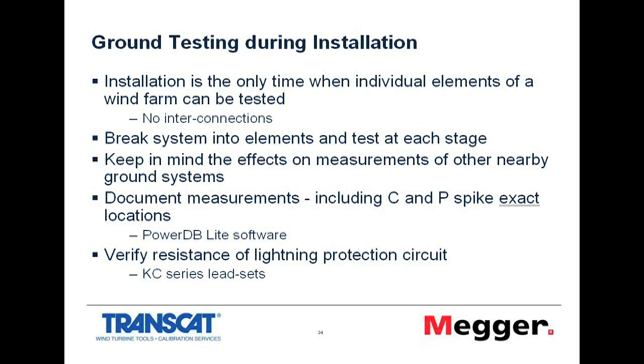In addition to that, when you're installing a wind farm, it would also be very important to verify the resistance of the lightning protection circuit. That is the resistance from the lightning receptor at the wingtip right down to the earth point in the base. Typically this resistance needs to be 25 milliohms or below. Okay, for that we also have a set of test leads, the KC series, but I'll mention a little bit more about those in a moment.